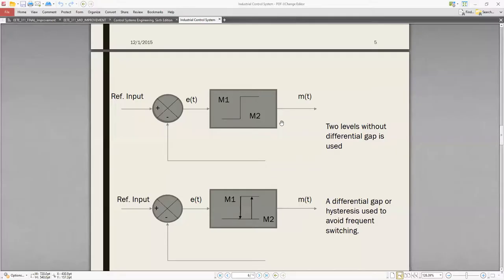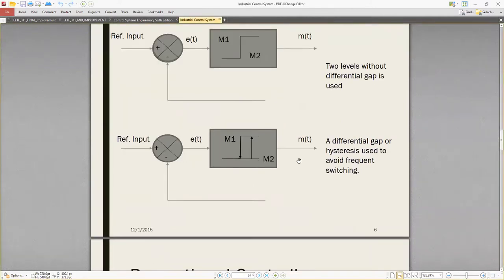The reference input is at a certain level; m1 is one level, and m2 is the other. Two levels without a differential gap can also be used. A differential gap, also called hysteresis, is used to avoid frequent switching.